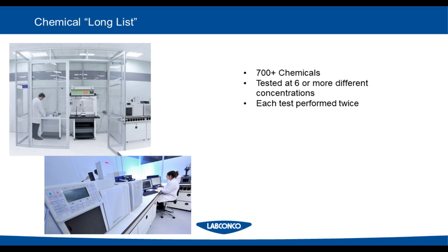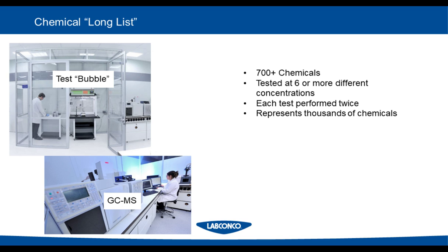So we're absolutely confident in our capacity charts, and we know exactly how much we're going to capture before you're going to have greater than 1% TLV breakthrough on that filter. And again, they represent thousands of different chemicals, not every chemical, and so if you've got a chemical that's not on our long list, we absolutely can review that and even test that in this chamber in our laboratory. So that's the test bubble, that's the GCMS, which is no great deal, everybody knows that. It's just a very large investment for us in testing instruments, but very much required.